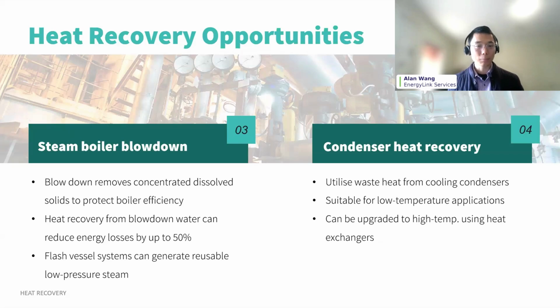Condenser heat recovery will be especially relevant in refrigeration or vacuum systems. Condenser water might exit at, say, 30 or 40 degrees Celsius, and while it's low-grade heat, it can be repurposed to preheat water. For example, boosting hot water inlet temperature, and then with the right heat exchanger, this can offset some gas or electricity heating loads, mostly gas in this particular case. This will be quite relevant in the food and beverage sector, where there's a high cleaning or process water demand.